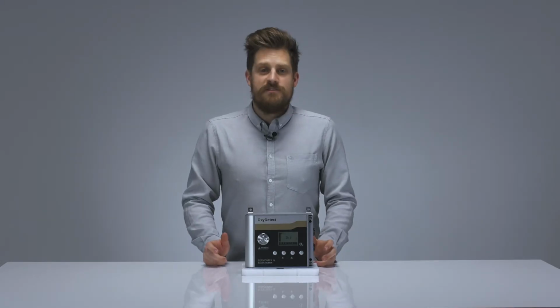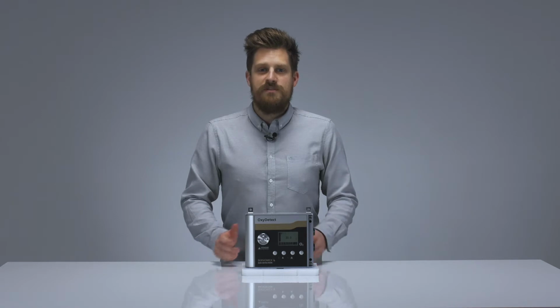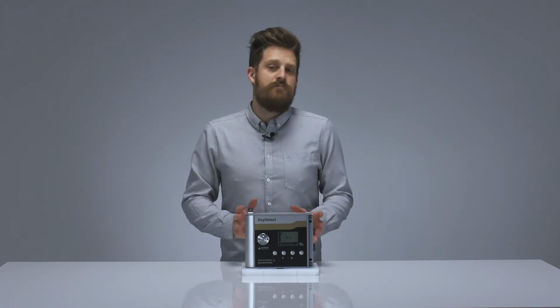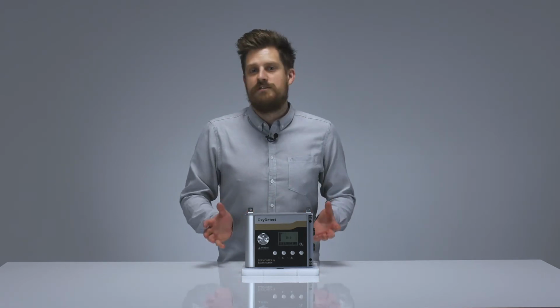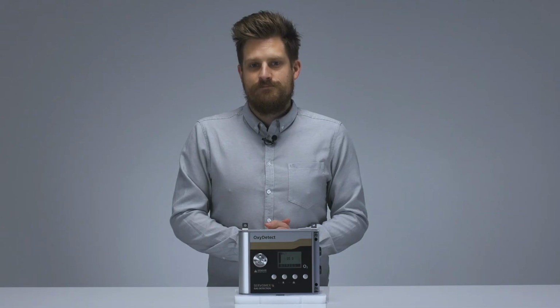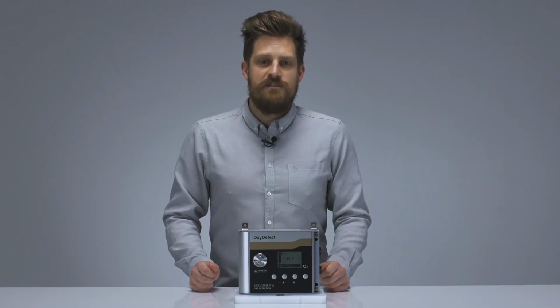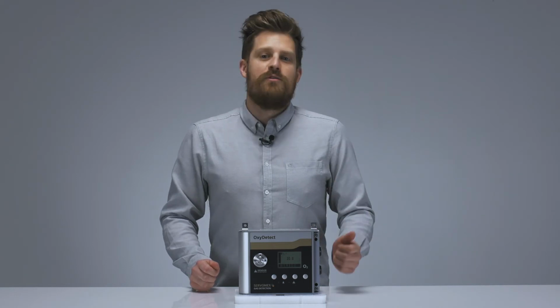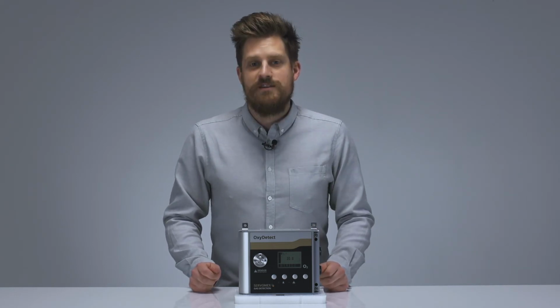The OxyDetect is designed to be a fit and forget product, which means it needs no service contract and only requires periodic calibration every 3 to 6 months, which can easily be performed by the user. It uses non-depleting paramagnetic technology, which needs no replacement or top-up, unlike traditional electrochemical oxygen gas detectors. Of course, if you do need maintenance or advice, you can contact Servomex's global service network.